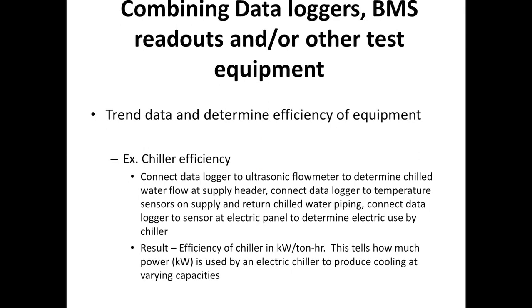So when the chiller was at peak conditions, when it was using the most electricity, we know how much electricity was required for peak capacity. And we also know part load conditions based on supply and return temperatures and looking at the volume of that chill water flow and how much electricity was required by the chiller.